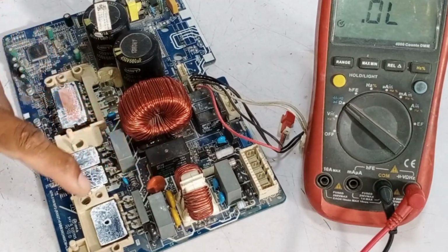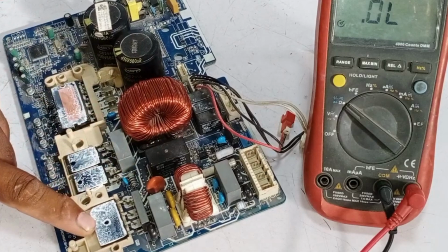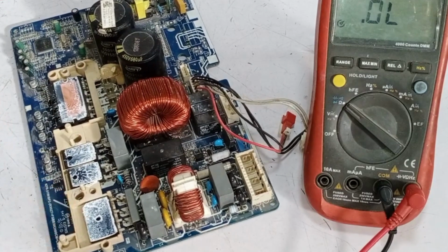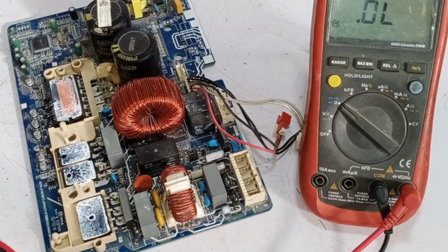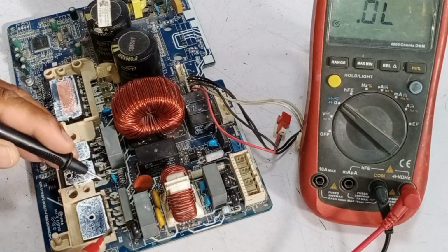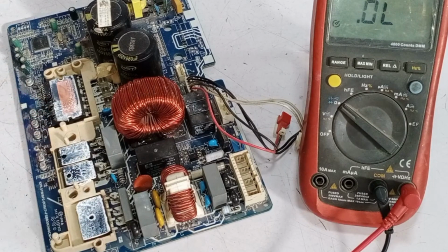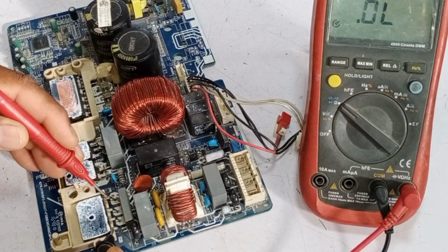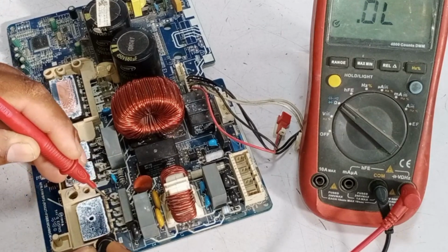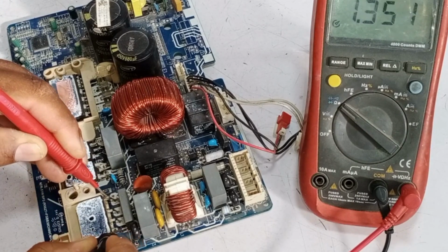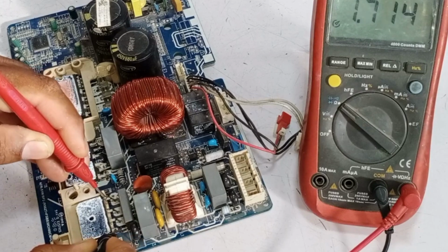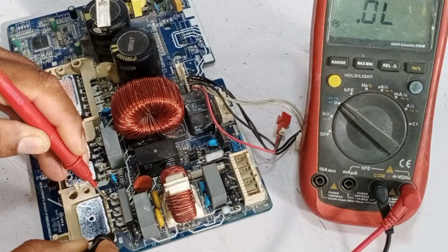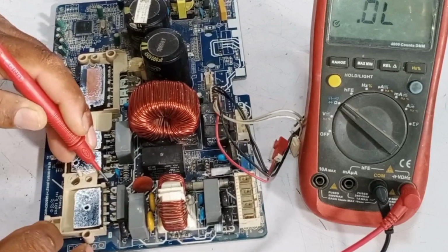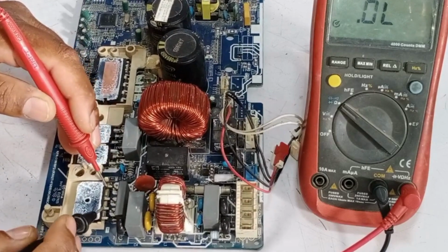When electricity passes through the PTC sensor, it enters the bridge rectifier, where the AC is converted to DC. Now let's check the bridge rectifier. Place the positive probe on the positive pin and the negative probe on the negative pin. The voltage drop on the multimeter on this polarity should show for a short while and then disappear. As you can see, it showed a voltage drop and then disappeared, which indicates it's working as expected. After this, let's check the next points.